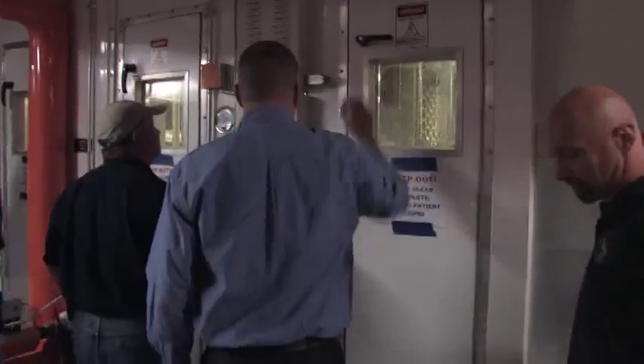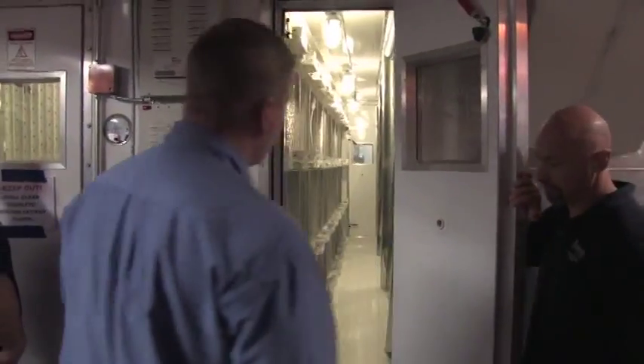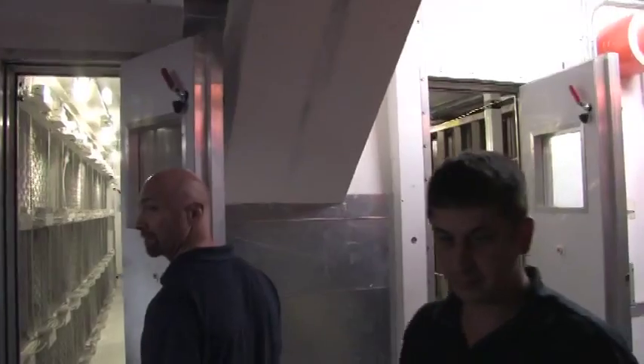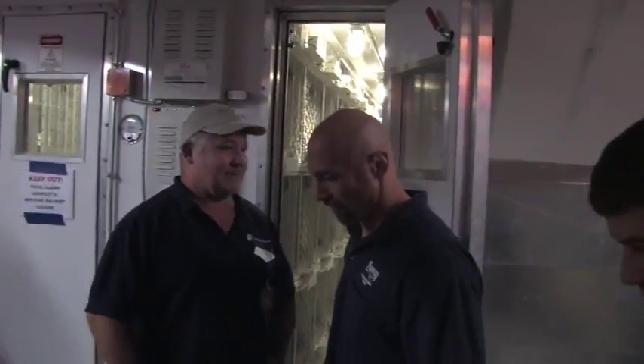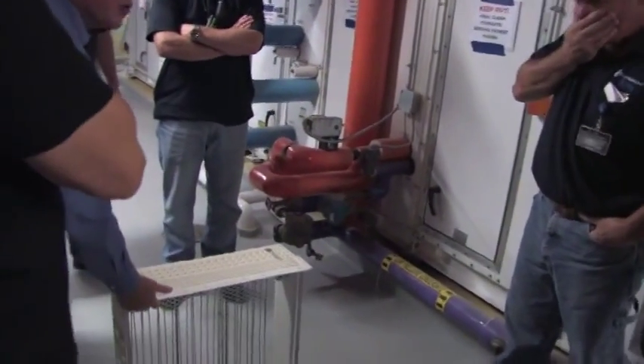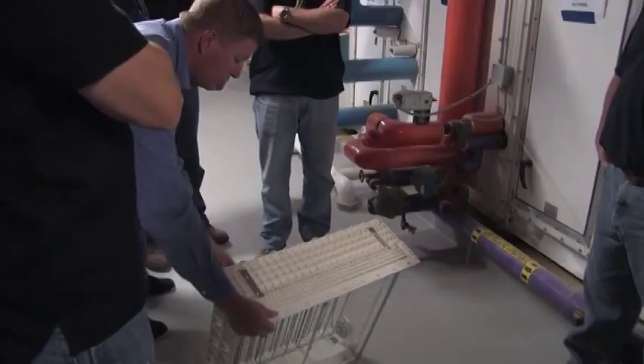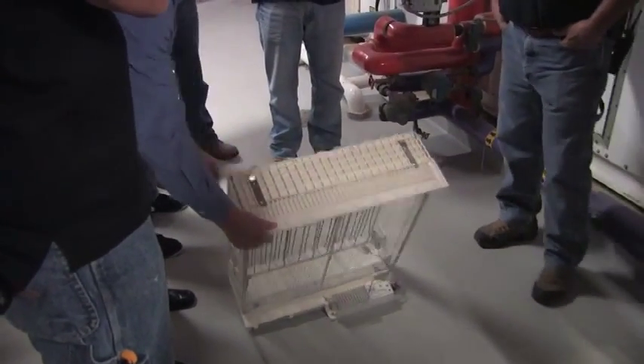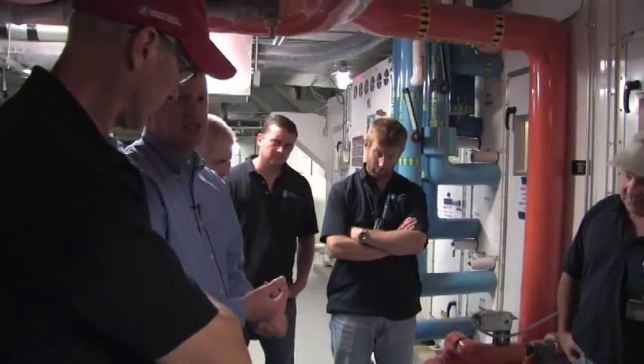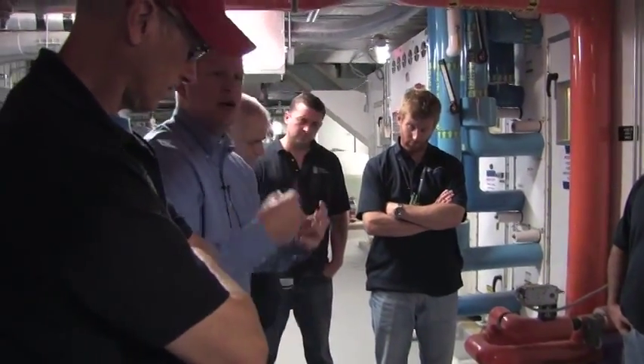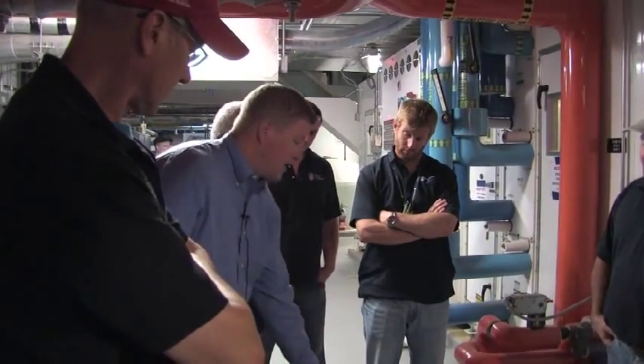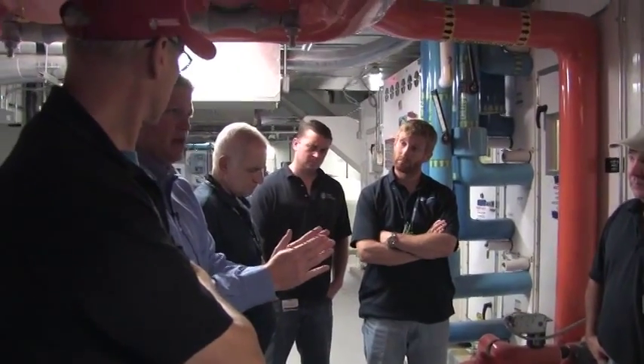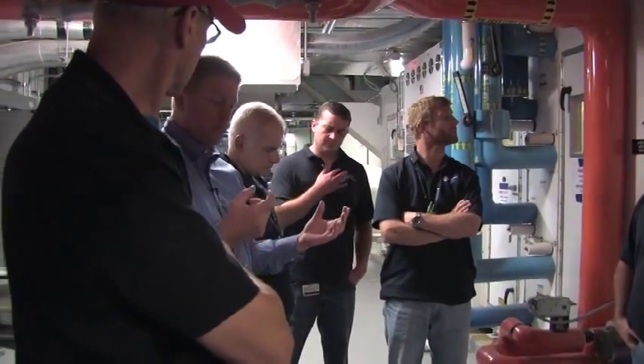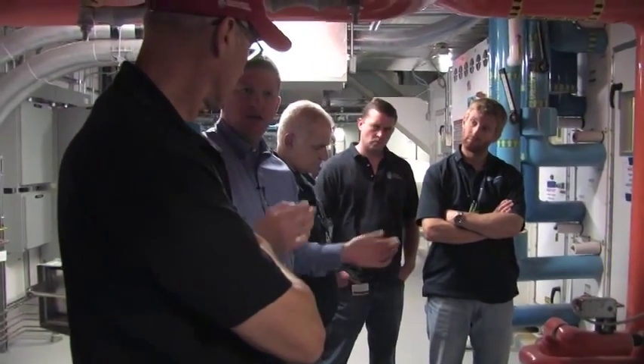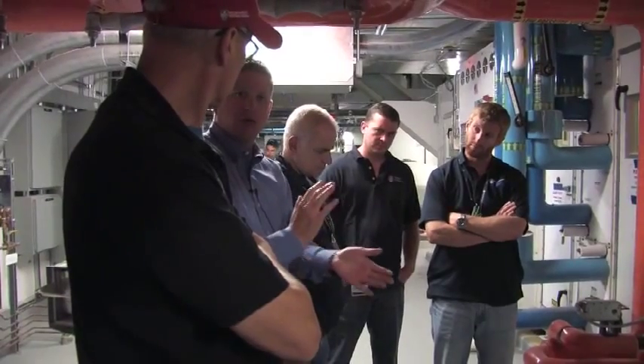Here we have our electronic filtration. All the way down. Any concerns with this? Here's actually one of the electronic modules. Air is going to go in through this side. It actually gets charged inside here by these, you can call them probes. So think about electricity, opposites attract. In this field here, the particle is charged to be positive. And then on the downstream side, there's about a 6-inch piece of media, and you'll see there's metal clips on the bottom of them. It's charged negative, so it actually causes the filter media to attract the particles to it.